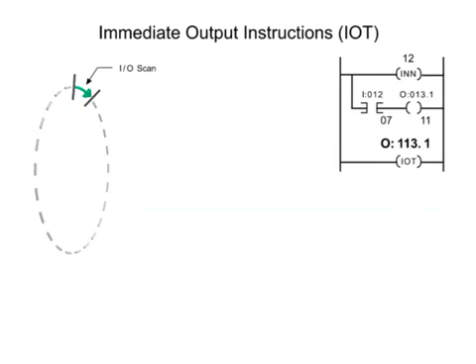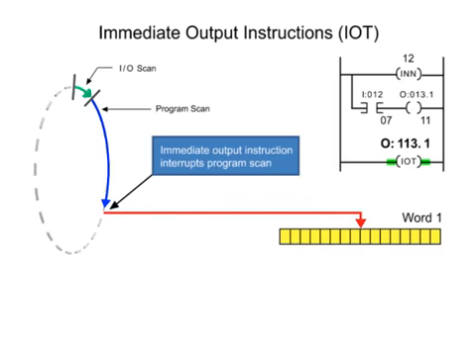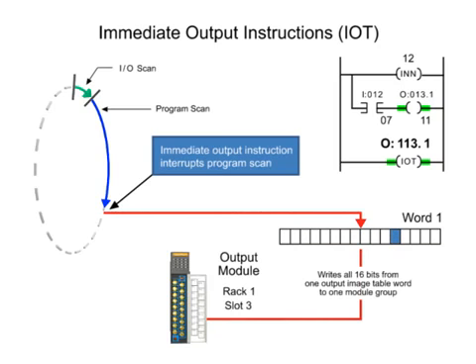The immediate output instruction operates similar to the immediate input instruction. As the scan is interrupted, the bits of the addressed word are updated and the field outputs are energized or de-energized according to the output image table.